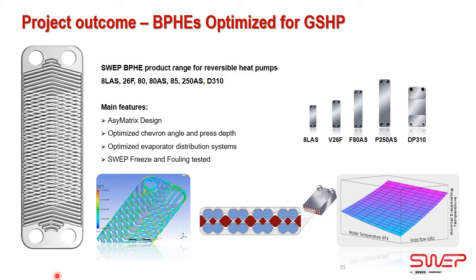We are using the AsyMatrix design, lowering the water pressure drop. We have optimized the chevron angles and design of the plate based on what we have seen with the CFD and the freezing tests. We are working with several different types of evaporator distribution solutions that assure that the refrigerant is going into the right channels. And all of these units have been freeze and fouling tested, so that we are able to help you with the operating envelope to avoid freezing.